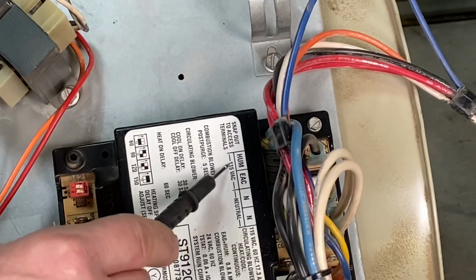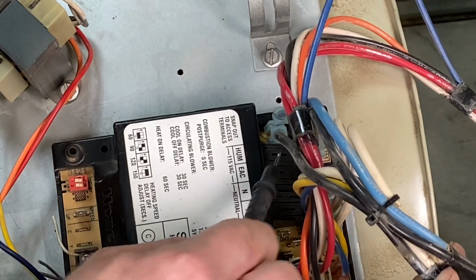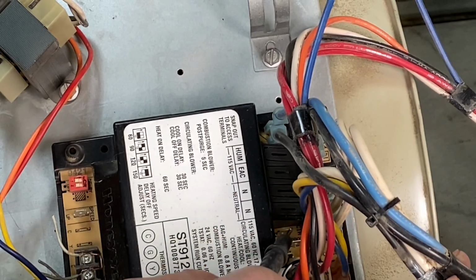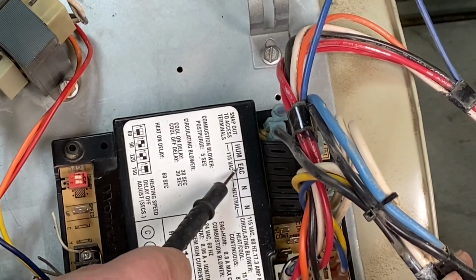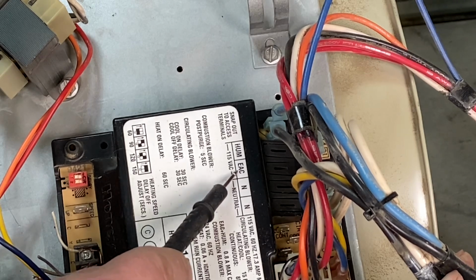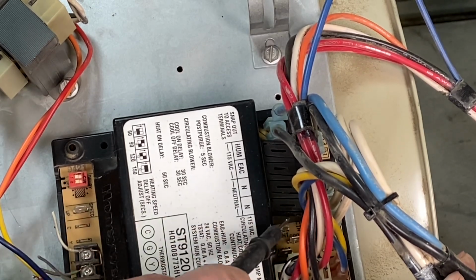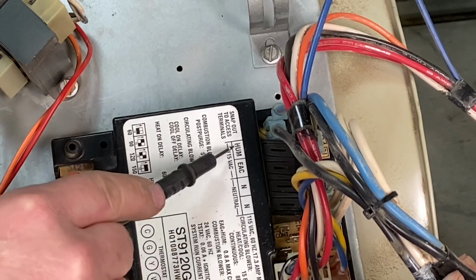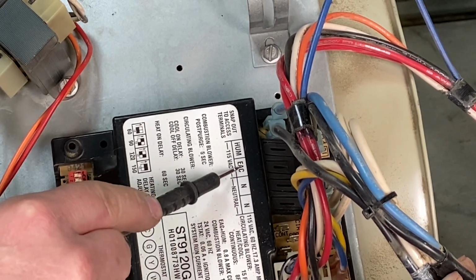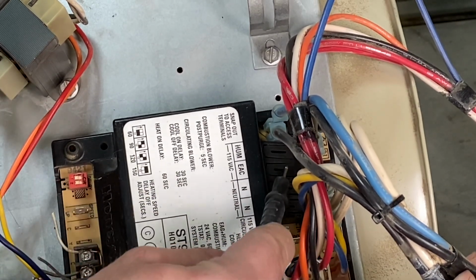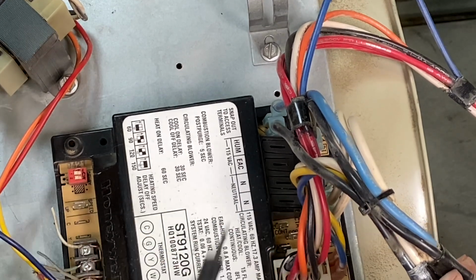If we had a humidifier accessory installed, we could install it between this terminal and also neutral over here. If we had an EAC, electronic air cleaner, we'd put it between this terminal and also neutral over here. So humidifier and neutral, electronic air cleaner and neutral. These are all covered up. We're not using those terminals right now.